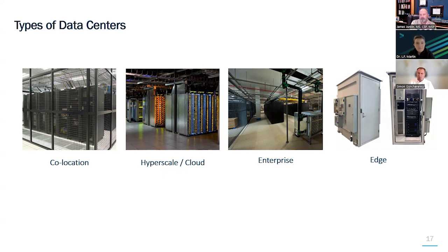This reminded me of conversations about fire extinguisher access. A lot of these facilities complete the building, bring the fire marshal in, and he looks at this huge open data floor with a fire extinguisher within 75 feet of any spot, and approves the room. The moment he leaves and they start selling the space, barricades get erected everywhere, so now you might have to go from one cage to another 500 feet before reaching the closest fire extinguisher. That's a conversation we've had lots of times, telling people to think about what happens between when the fire marshal left and the current situation.